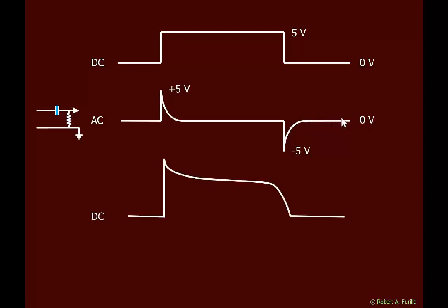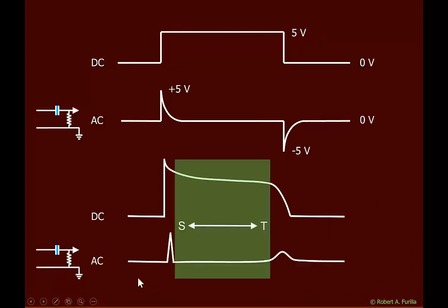If we look at a ventricular action potential, we see it's a DC voltage. We start at zero, it jumps up, it's held high, and then falls back down — not very different from our DC signal. If I run that through an AC filter, we see no change at zero, then a rapid increase producing a spike, which returns back to zero because the AC filter, depending on the cutoff frequency, sees little or no change during the plateau and returns back to zero.